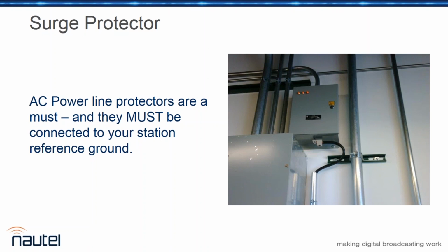The AC wiring is typically going to be the choke point. Most surge protectors won't take an AC wire above about 6 gauge, so you've got fairly high inductance per foot, and keeping it as short as possible is definitely to your benefit. There are high-end surge protectors called series devices where you pass the entire 3-phase or single phase through them. They're arguably the most effective if you provide them a good ground, because literally everything has to go past them to get anywhere else. But those, you're talking bucks for one of those, getting into the thousands of dollars.